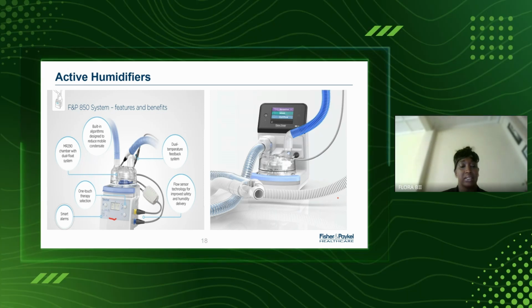Besides that, you have what we call the finger guard. Now, the finger guard is just a guide that can be used by depressing it to push the humidification chamber, which is this portion here. Now, why is it important to have a humidification chamber? Because this is absolutely where all the magic happens. So when you have gas that is coming from any flow source, for example, a ventilator, it would be drawn in, and remember that gas is very cold and very dry. So it would be drawn in by a part of the circuit we call a dry line. And once it gets into this humidification chamber, the chamber itself has sterile water in it.